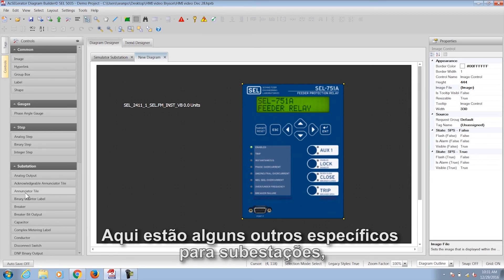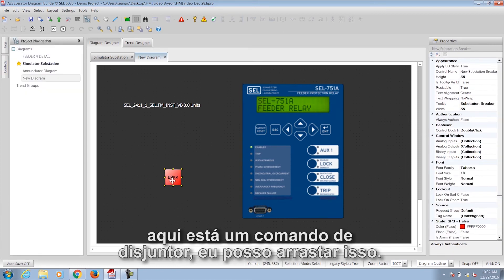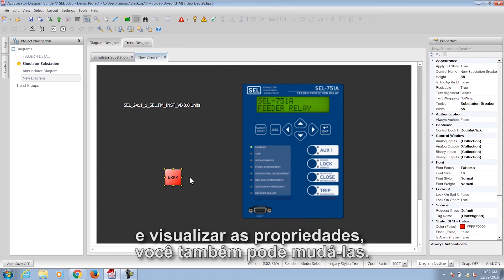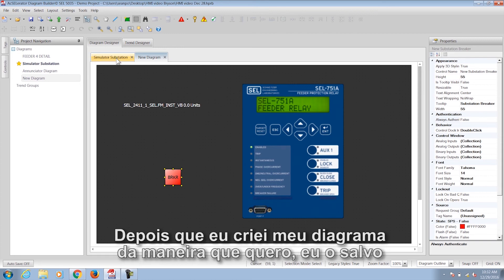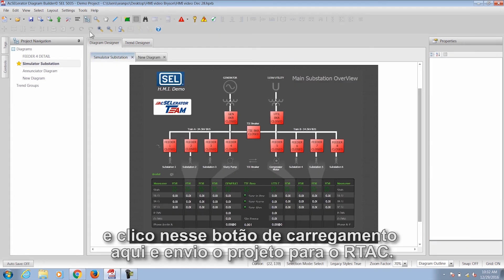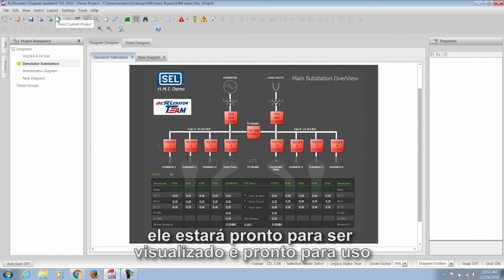Here are some controls specific to substations. Here's a Breaker Control — I can drag that over, click on the Properties tab, and view or change the properties. After I've designed my diagram the way I want to, I save it, then click on the Load button and send the project to the RTAC. After the project is sent to the RTAC, it's ready to view and ready to use.